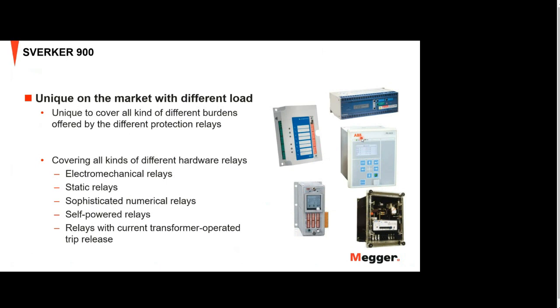Static relays are difficult because it could be resistance, quite high resistance. Sophisticated numerical relays, they are very low resistance load, but the tricky thing with them is that they are very accurate, especially when you're testing on low current.